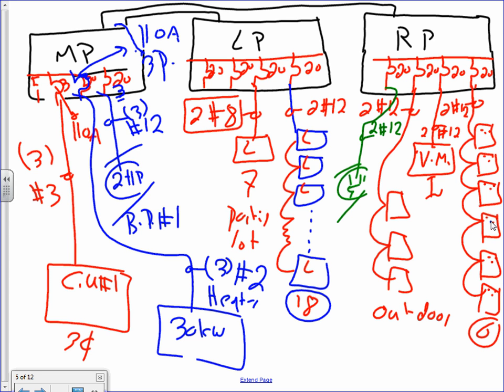Now, when we move to the main panel, these are big boys. In the main panel, there will be big boys here. Big boy number 1 is the cooling unit. Cooling unit, that's a big boy. It's a dedicated circuit. It's 110 amps and 3 conductors number 3. Where the heck did I come up with this? You're going to see the calculation that's coming. Very easy. Then a 30 kW heater.